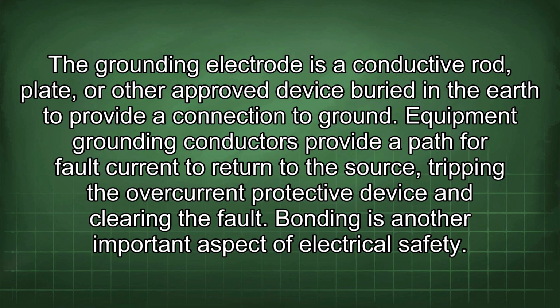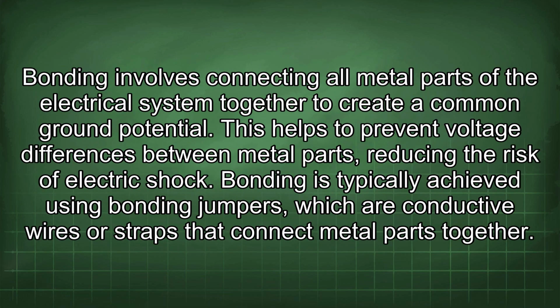Bonding is another important aspect of electrical safety. Bonding involves connecting all metal parts of the electrical system together to create a common ground potential. This helps to prevent voltage differences between metal parts, reducing the risk of electric shock. Bonding is typically achieved using bonding jumpers, which are conductive wires or straps that connect metal parts together.